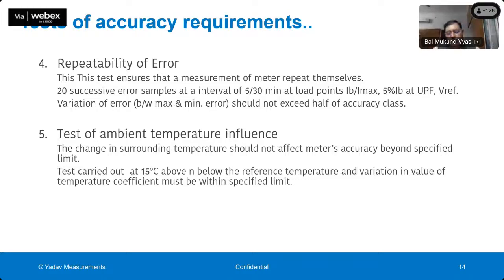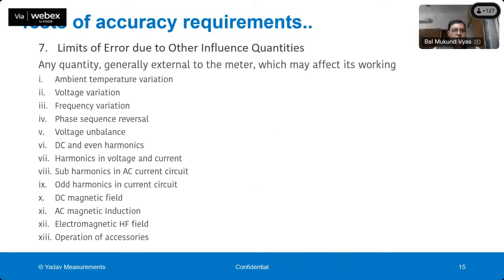The accuracy of the meter is tested at different temperatures in an environmental chamber, and the variation in the error is compared with the error at 25 degrees centigrade or 27 degrees centigrade, which is the reference temperature, right?